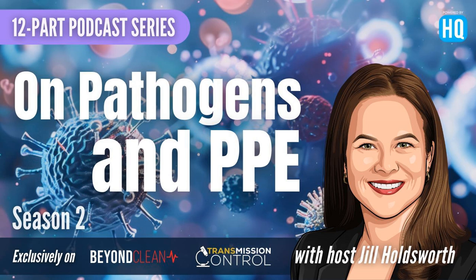No, exactly. As you indicate, every instruction for use, or IFU, says to do visual inspection. So the only way to visually inspect inside any lumen is to use some kind of borescope. But again, as Cheron mentioned, some manufacturers say in particular to use a borescope, for example, for the shavers. But the other issue is that when they say you cannot really prove that it's causing infection, we had documented cases. The one that we had in Methodist Hospital in Houston in 2009, CDC said that the infection was caused by the use of the shaver. So that's how we actually started on the issue of using a borescope.